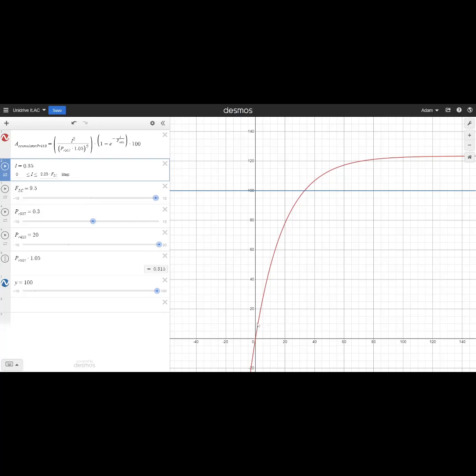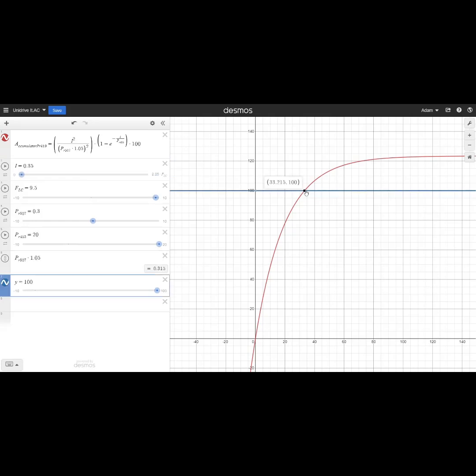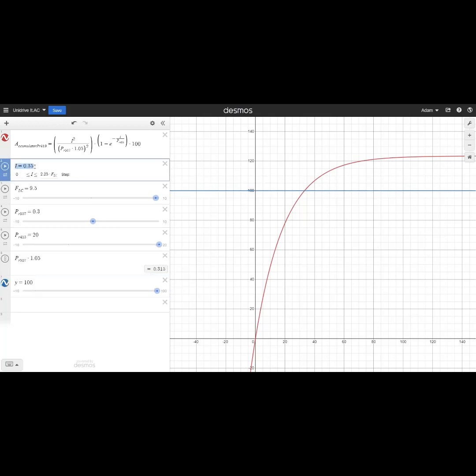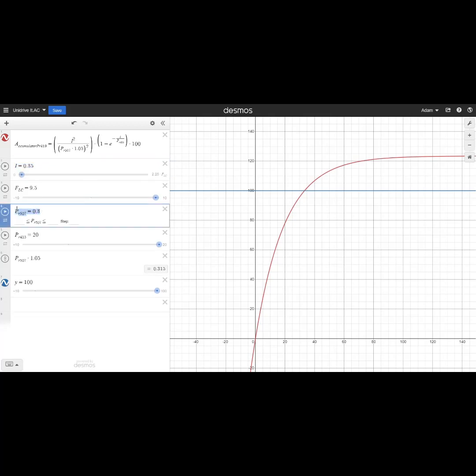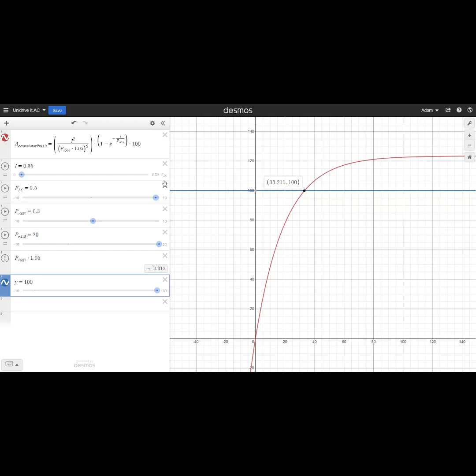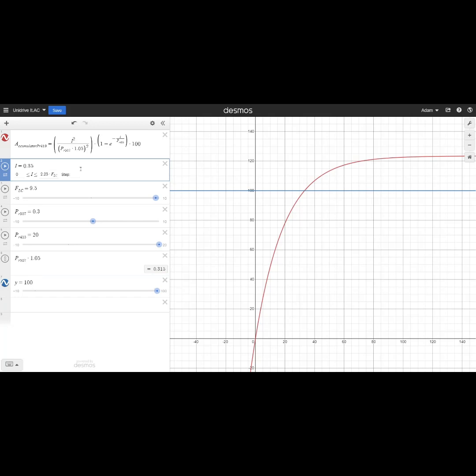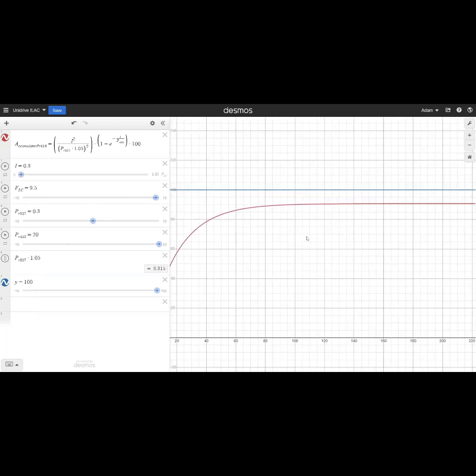In Desmos, we can see the curve rises sharply in the beginning and then levels off towards a limit. This graphed curve is the accumulator's value. The blue line here is where the accumulator will hit 100 and the drive will trip. The x-axis tells us time in seconds. We can use the crossing of the accumulator's value with the value of 100 to tell in seconds when the drive should trip. You can see from my variables on the left, my current that the drive sees is greater than 105% of the motor's rated current in parameter 507. So with such an overload and a time base set to 20, my drive should trip at approximately 33 seconds. As I turn the value that the motor sees down to less than 105%, the accumulator value levels off before it ever trips.